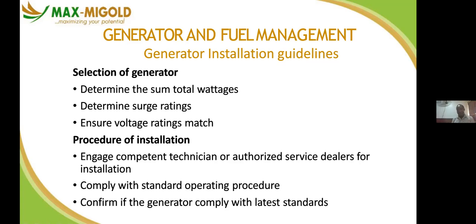withstand such occurrence. So what I expect you to buy when your load demand is 30 kVA is to go for 40, 50, go for 45 kVA to 50. So in that range, you have a tolerance to play with of about 5 or so.